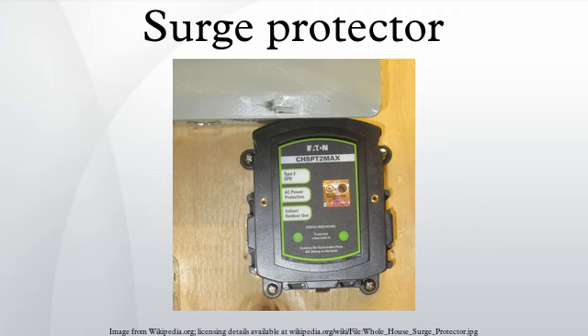A surge of any arbitrary ampere and voltage combination can occur in time, but surges commonly last only for nanoseconds to microseconds, and experimentally modeled surge energy has been far under 100 joules. Well-designed surge protectors should not rely on MOVs to absorb surge energy, but instead to survive the process of harmlessly redirecting it to ground. Generally, more joules means an MOV absorbs less energy while diverting even more into ground.